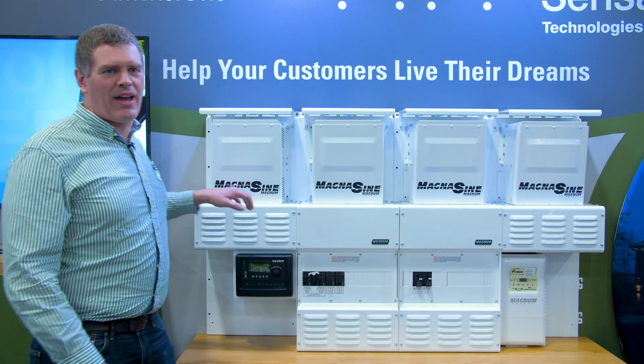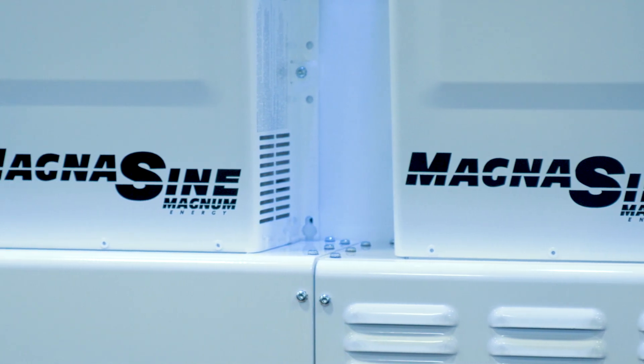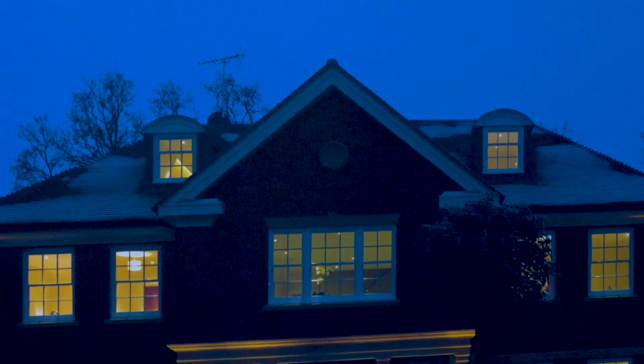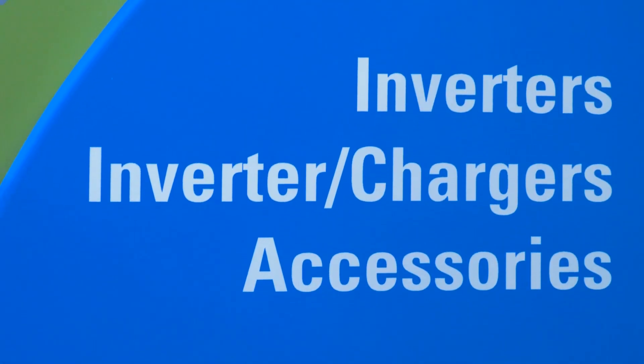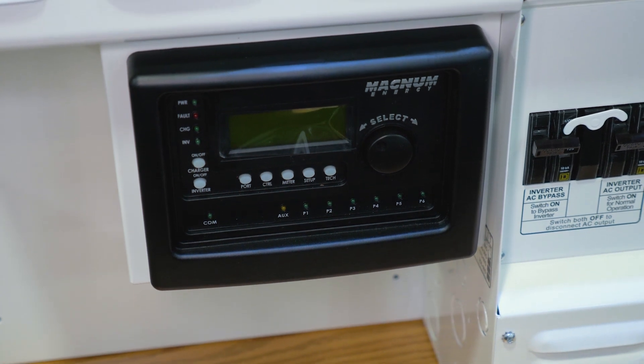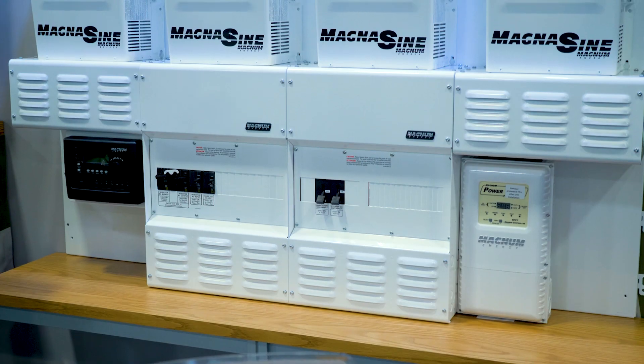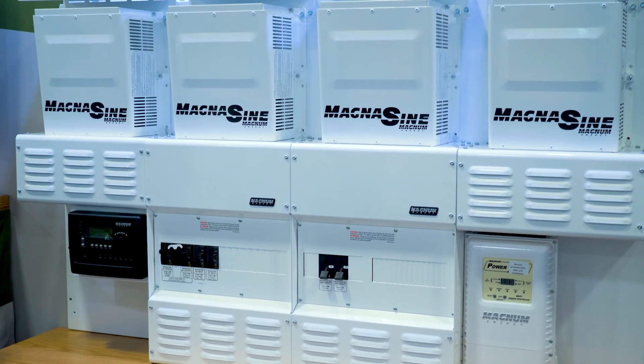This is compatible with our PAE series inverters — the MS4448 PAE and MS4024 PAE. The system intelligence is brought together by the MEARTR, or the advanced router. The total system output, if using the 48-volt products, is 17.6 kilowatts. With the 24-volt products, it's 16 kilowatts.